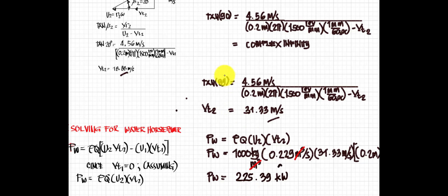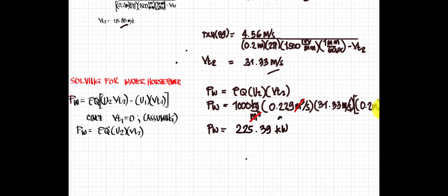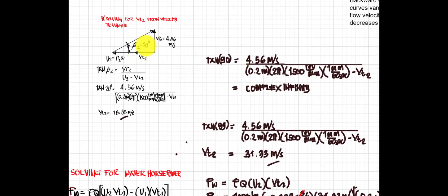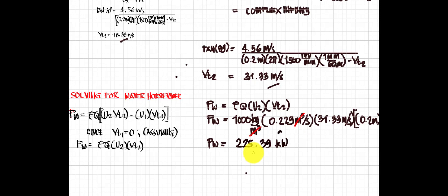Comparing at 89 degrees, we have 225.39 kilowatts — that's a large increase. As you increase the angle toward radial, the power also increases. From 20 degrees to 89 degrees, we have increasing power, which corresponds to an increasing electrical motor power and thus increasing electrical power consumption. In short, using a 90-degree or radial type blade is expensive in terms of electricity.